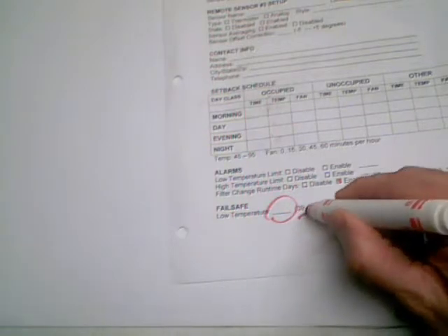There's actually a fail-safe temperature that is not shown anywhere in the interfaces. It's actually in the hardware itself of the unit, and it can be changed. But it says that if all else fails, if the programming fails, if the server fails, if everything fails, if it hits a certain temperature, it will turn the furnace on and let it run. And that can be set between 39 and 52, and I believe we're set at 45 as a default or something. But that's done right inside the unit itself with little jumpers, and it doesn't rely on any hardware or any software at all, so it's a very reliable fail-safe to keep us from freezing up.